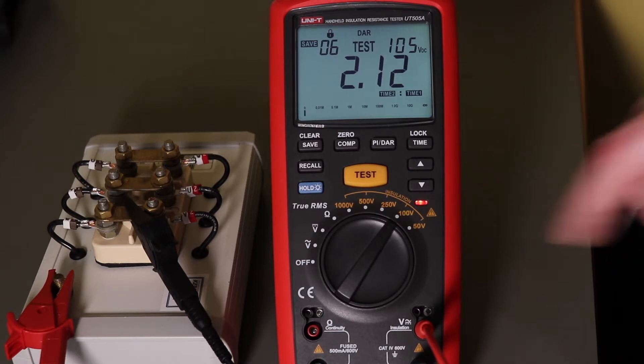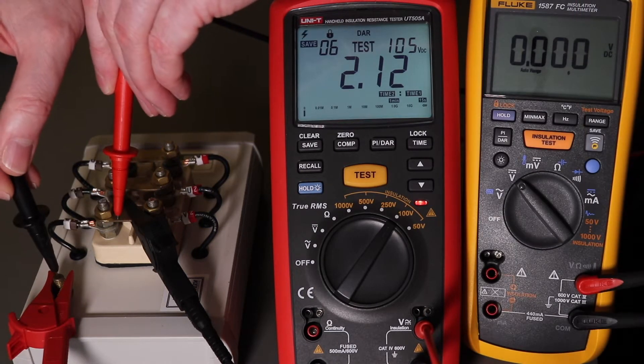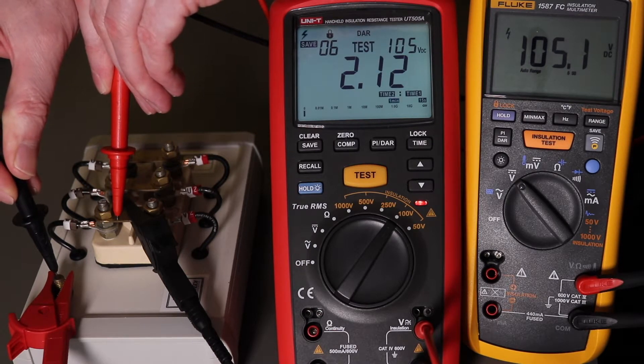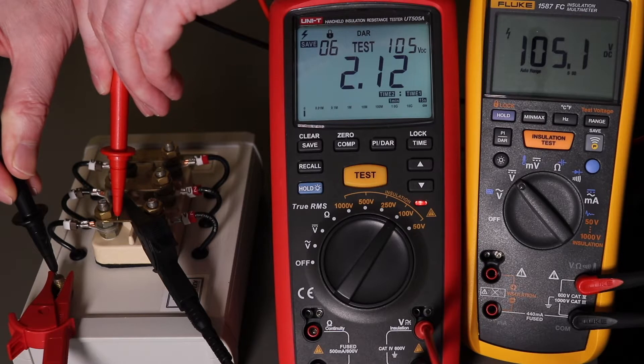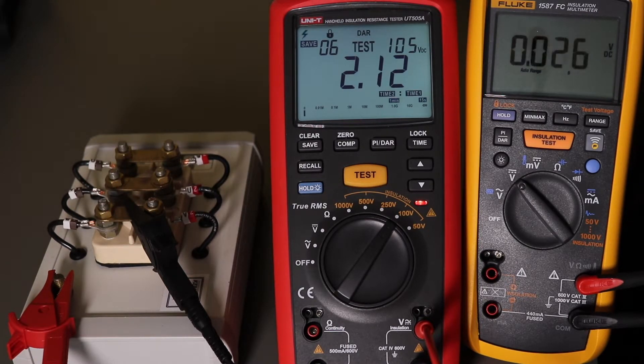And it's still got voltage coming out. Measure the output there - yeah, there we go. You can see 105 volts output on there. So the meter is still on but it's come to the end of the DAR test and it should have stopped, really.